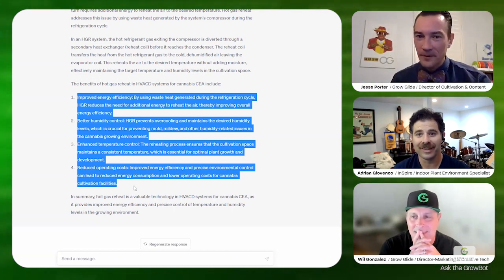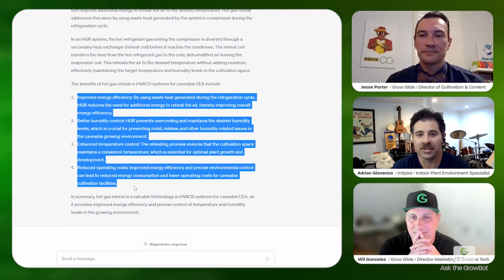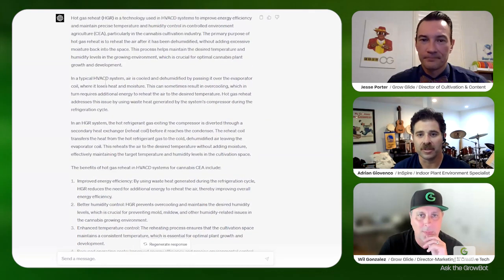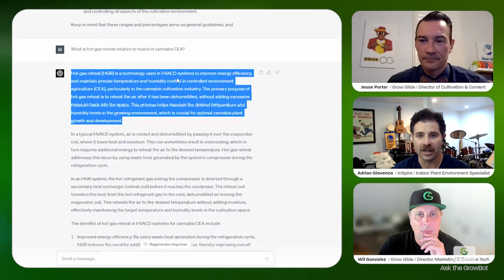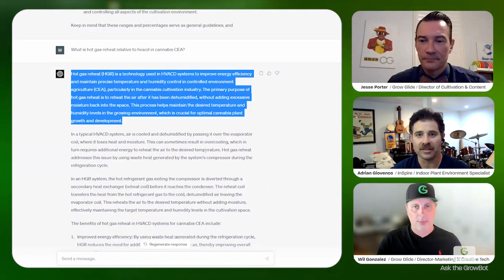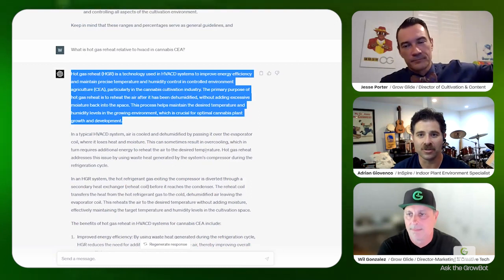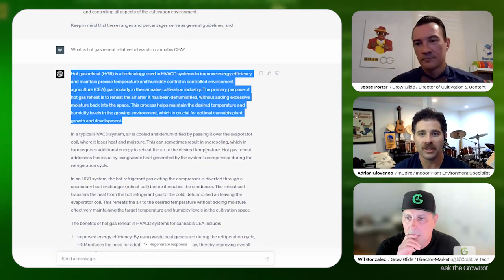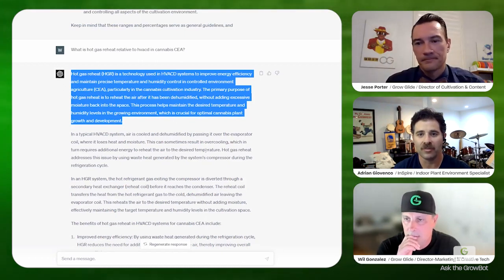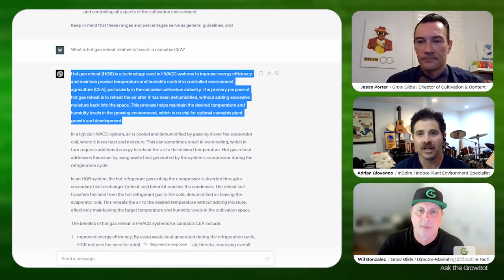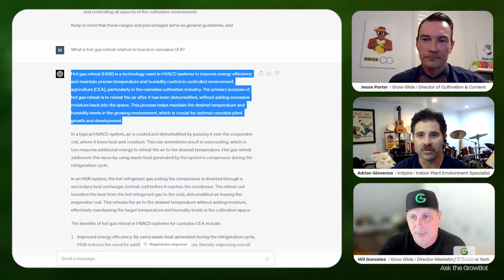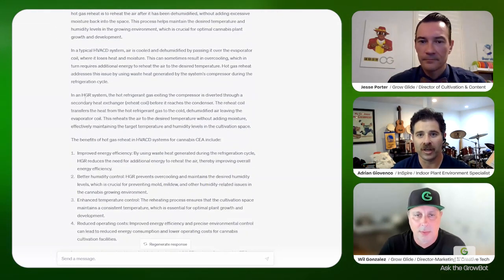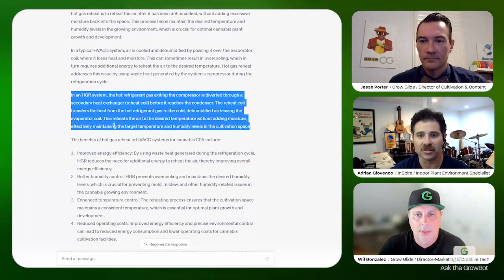In general, hot gas reheat is a technology that's been used for a long time in the HVAC industry, and it's effectively, when the compressors are running, instead of sending all of the heat and the refrigerant out to the condenser to be rejected, you divert it to a secondary coil. That's a heating coil inside of the unit, an additional coil. And there's a diverting valve, a hot gas reheat valve rather, diverting that so that you can take advantage of that heat basically, and use it as a first stage of reheat. That again is only available when the compressor or compressors connected to the hot gas reheat coil circuit are running.